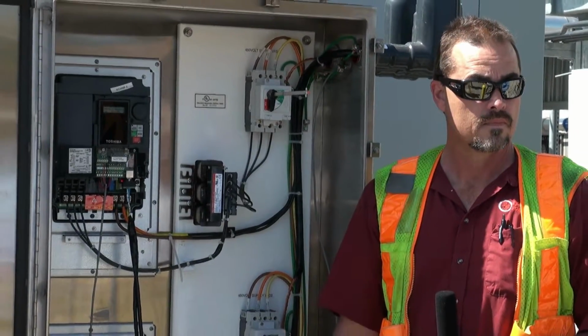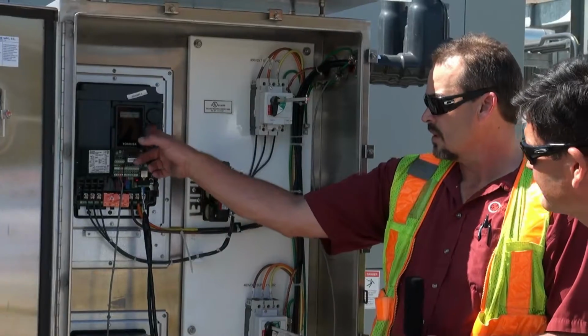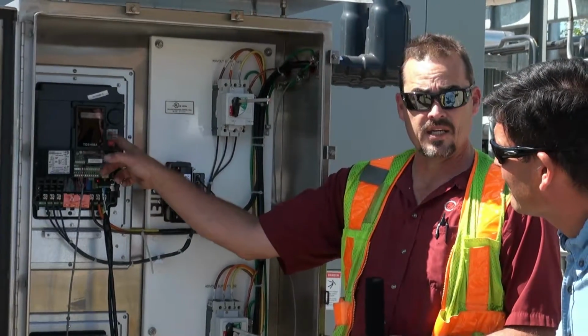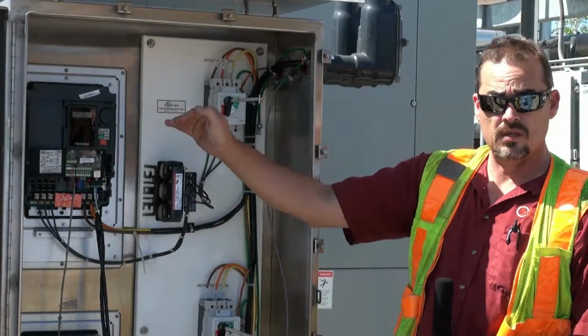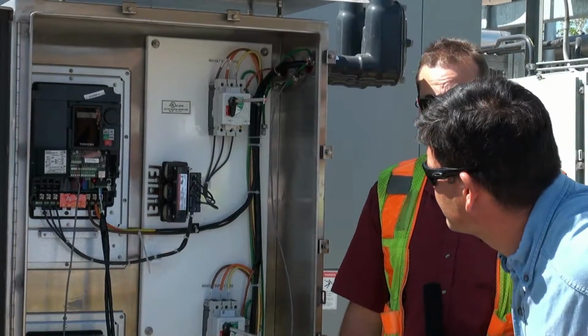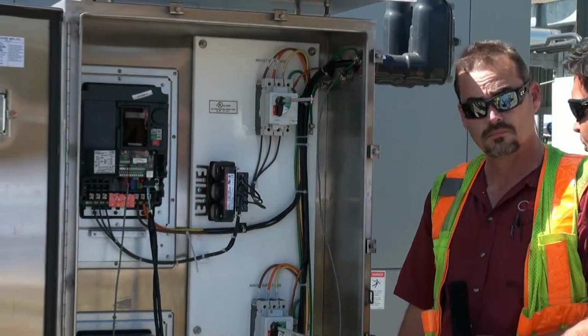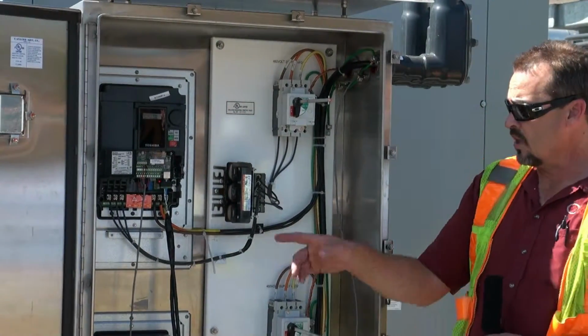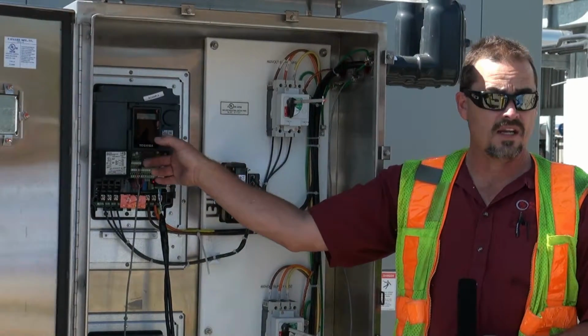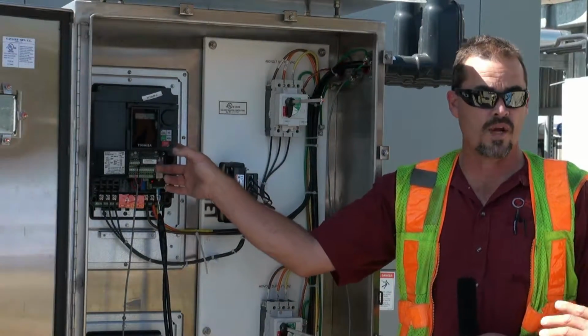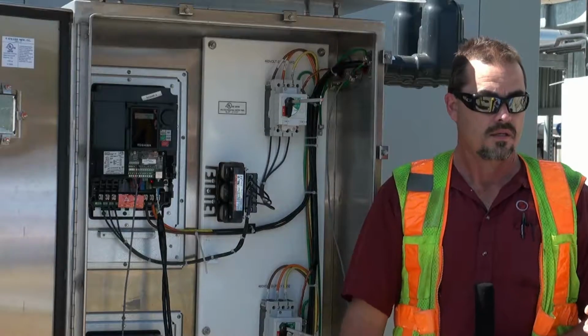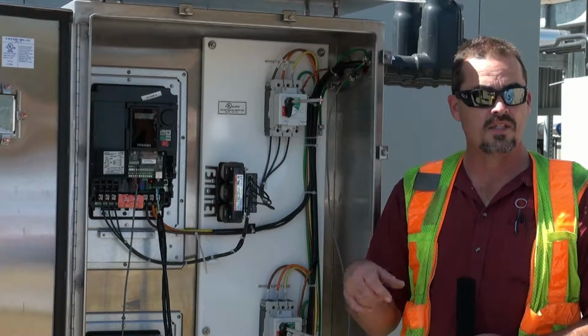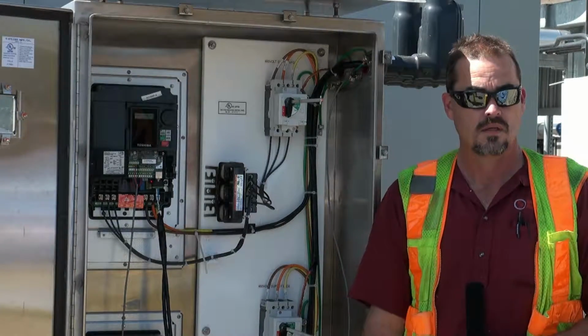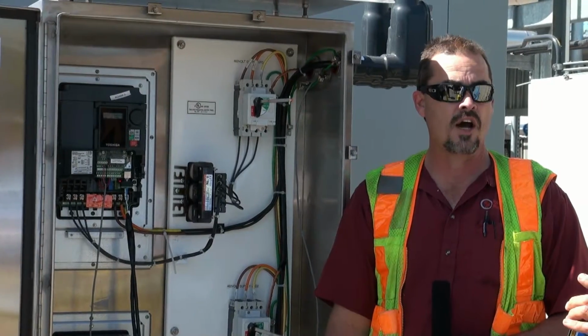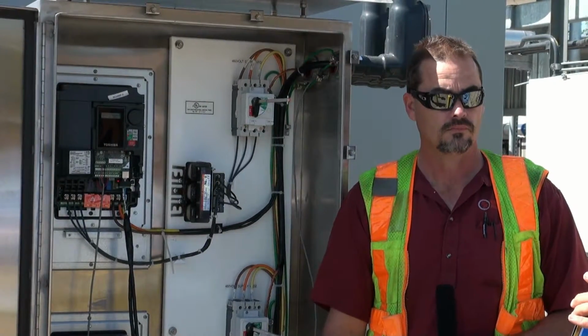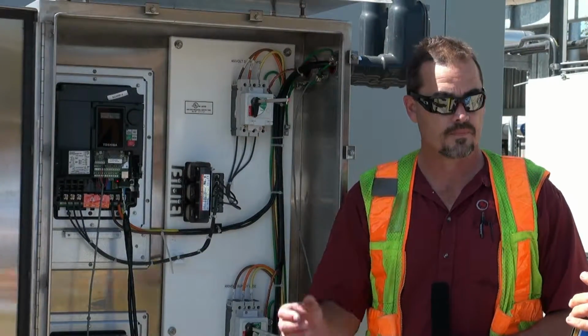So you push the local remote button, and the light comes on. The little light comes on. It's on right now. And then the run light will come on, but it'll be green. If it's green, you haven't pressed the run button yet. So then when you press the run button, it changes to red. And now that's in manual. Now you know it's running. In manual, yes.